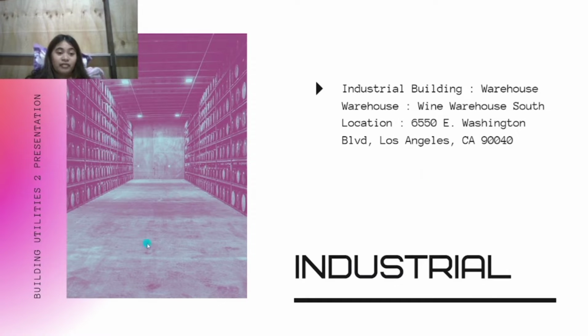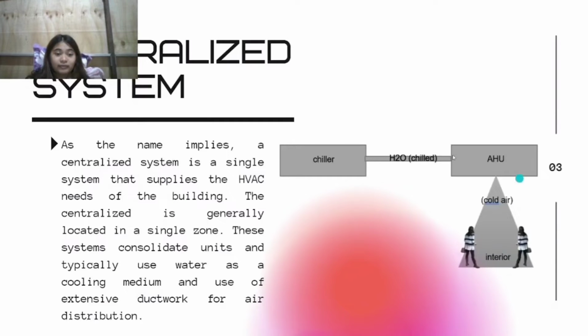So this is the picture of inside the warehouse. The Wine Warehouse, California utilizes a centralized system as the warehouse needs a large cooling capacity to maintain a certain temperature for beverages. As the name implies, a centralized system is a single system that supplies the HVAC needs of the building. The centralized system is generally located in a single zone. These systems consolidate units and typically use water as a cooling medium and extensive ductwork for air distribution. Some of the advantages of a centralized HVAC system are greater load management potential and better control of the system, while its disadvantage is that it is more sophisticated to operate and maintain, hence it is expensive to install.